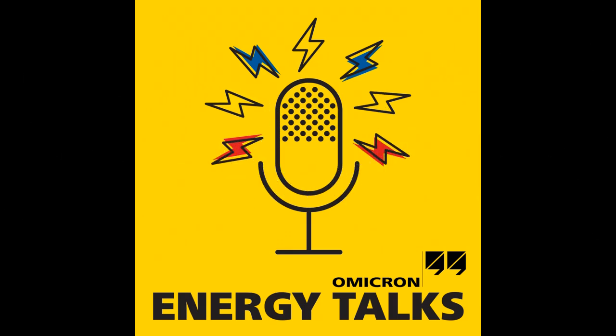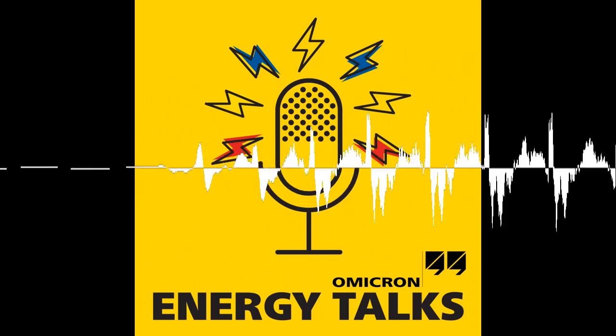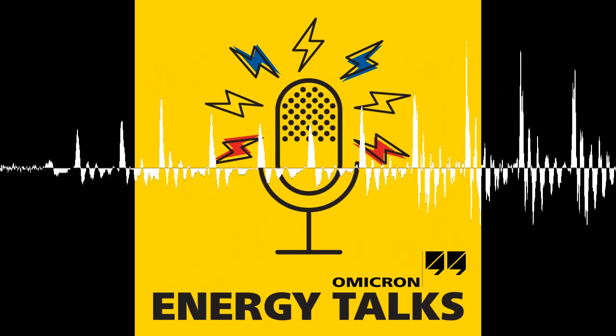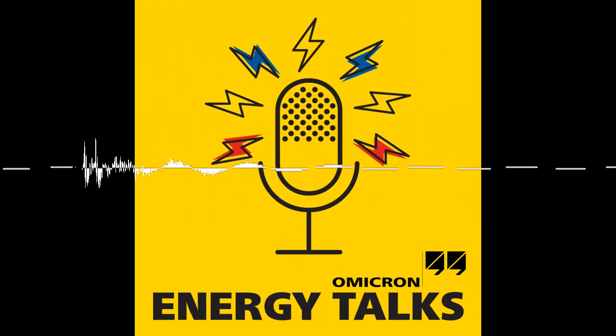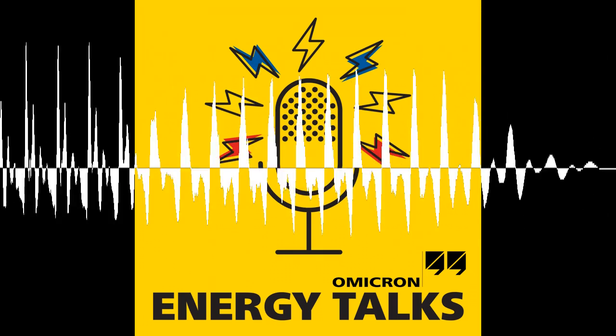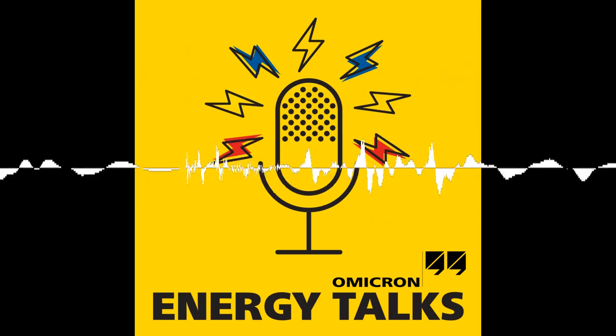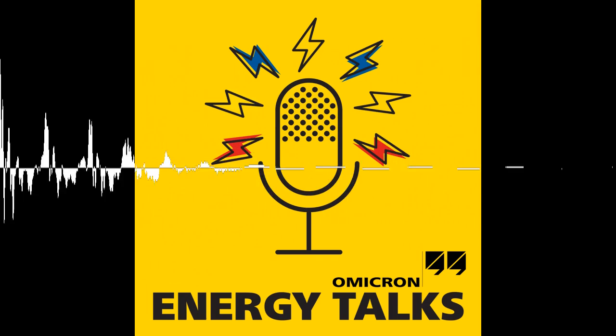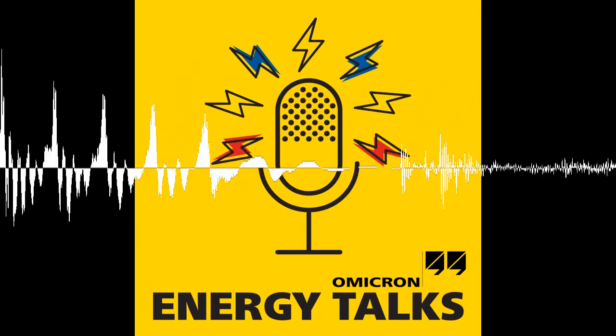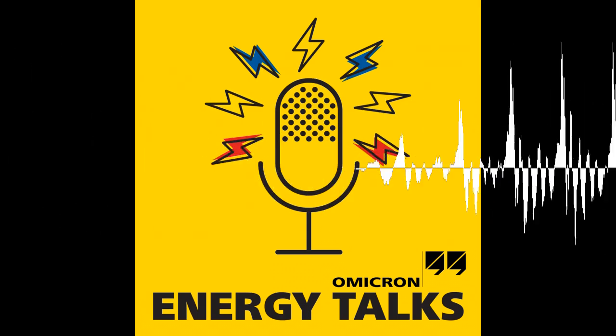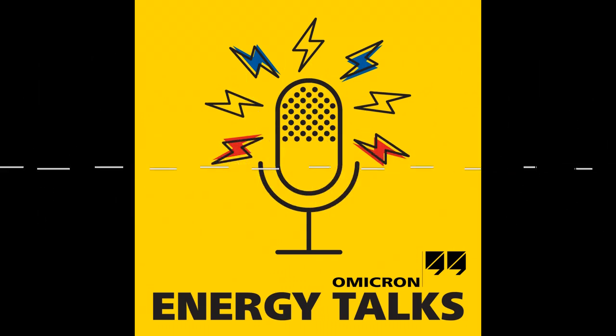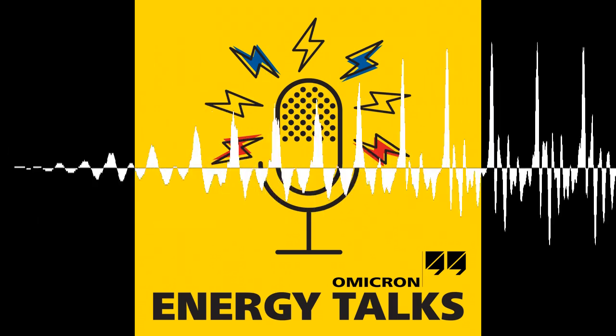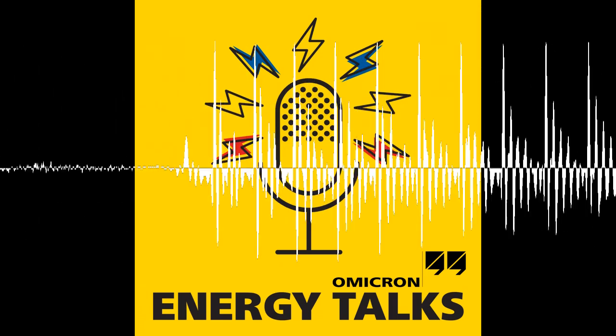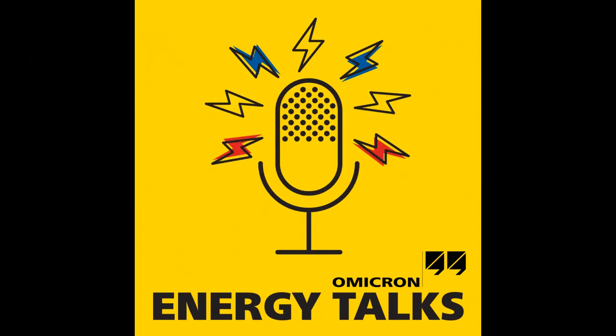Okay, interesting distinction. So how harmful is partial discharge activity in electrical equipment? Well, that really depends on the type of insulating system and your particular electrical energy asset. So for some, like rotating machines and generators with mica insulating systems, some PD is completely benign and it's totally tolerated. It's a normal part of operation. For XLPE or resin assets like, let's say, cables or cast resin transformers, that's where we want absolutely no PD in an ideal world. And yet for oil in transformers, particularly large power transformers, we're a lot more tolerant. So PD is, again, part of the process, but it should be within certain limits and bounds.